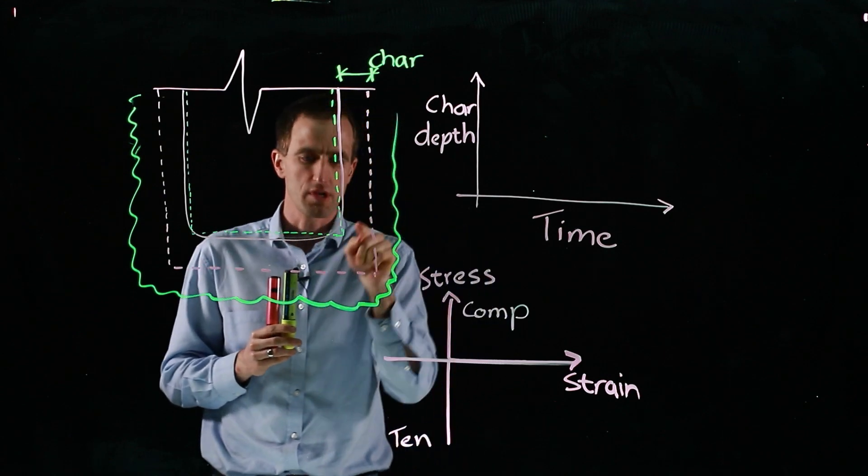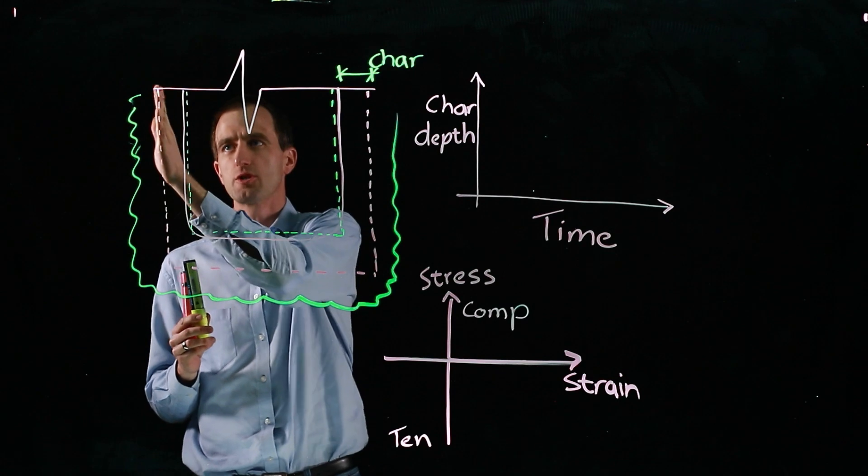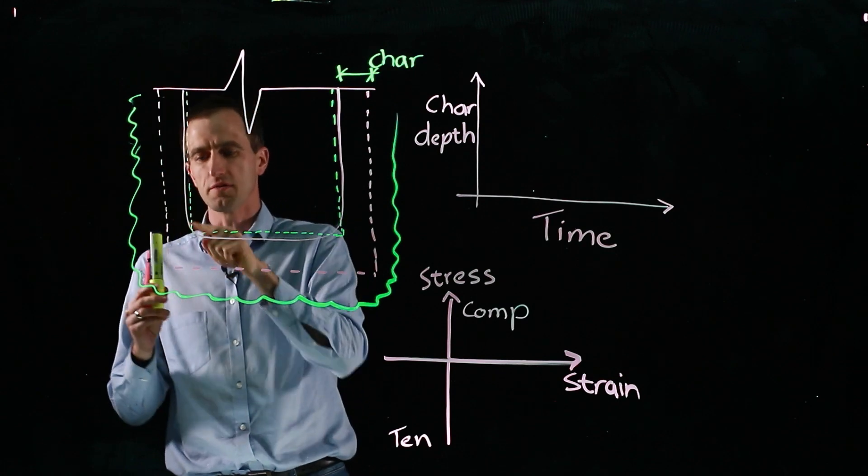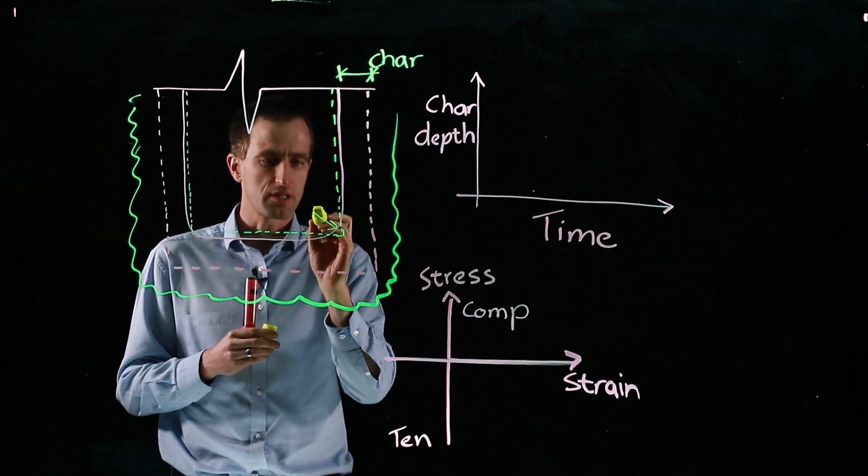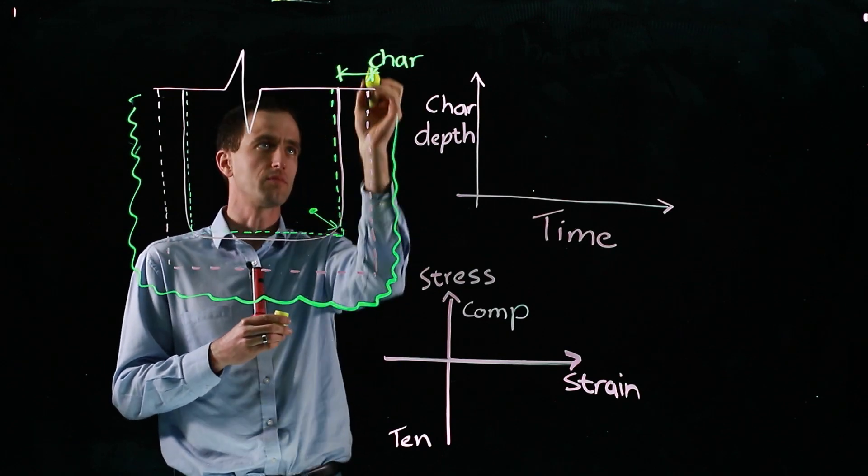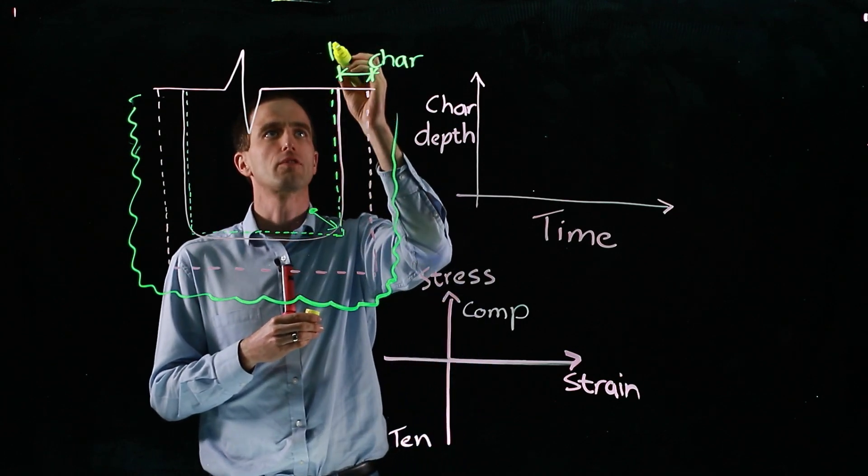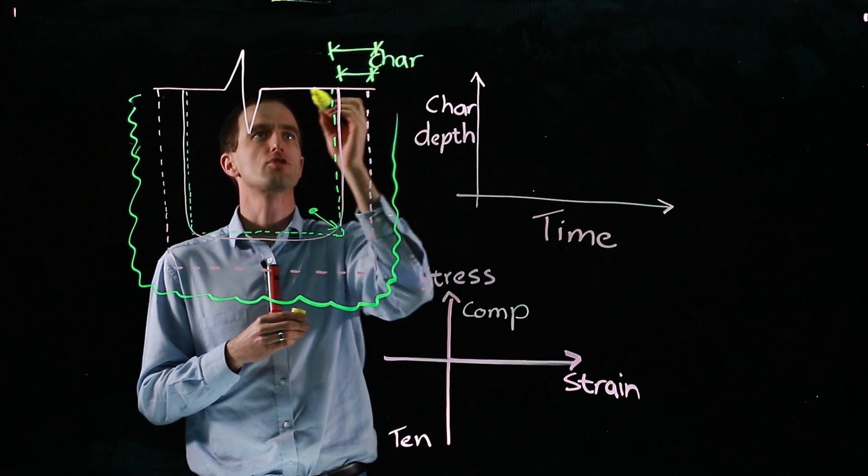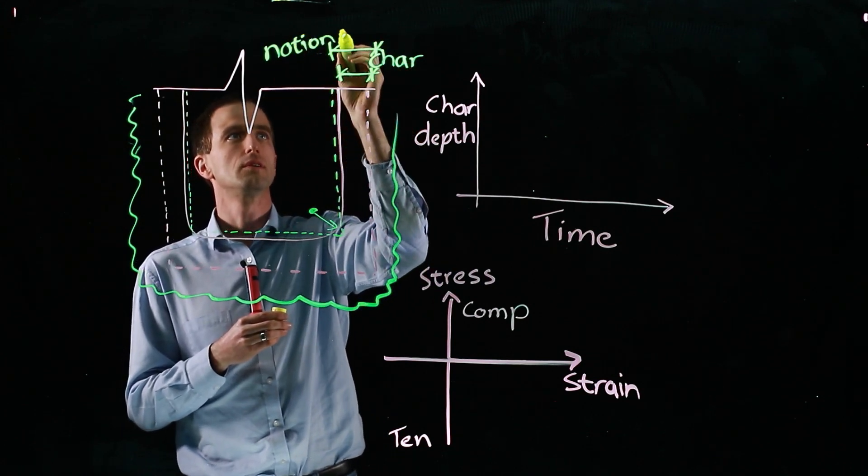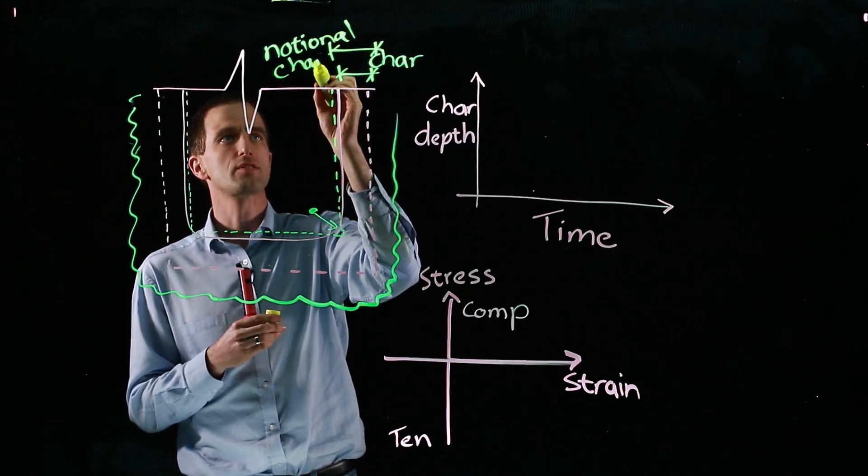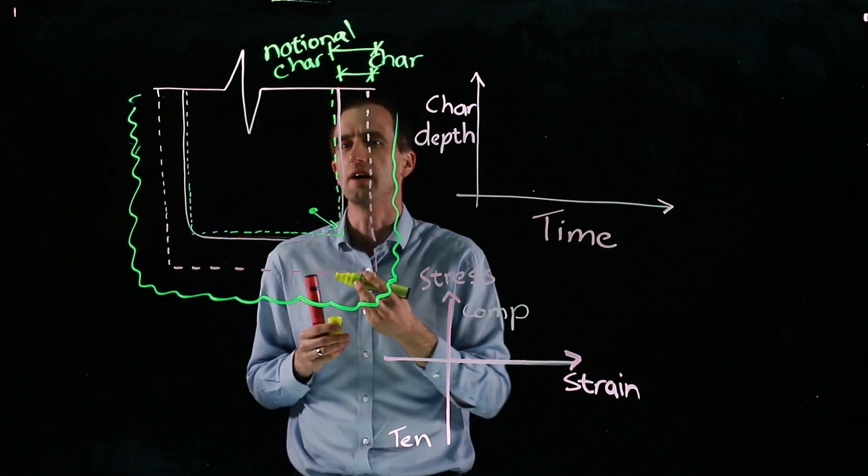But what happens at the corners, we also have a rounding effect as it penetrates. You've got one dimensional charring here, but at the corner you've got two dimensional charring. So we do have a radius that forms and we can take that radius as about the char depth that forms. But to account for the radius and other factors, we have what's a notional char depth there. So that's to include these other factors that proceeds as the fire continues.